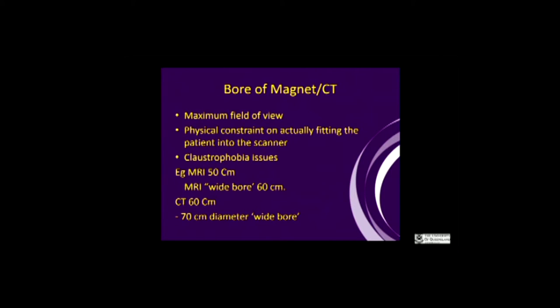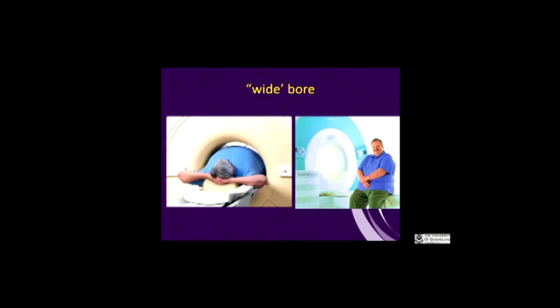The other physical effects are the actual diameter of the magnet or CT bore. 50 centimetres or 60 centimetres is actually quite narrow for an obese patient. MR had a 50-centimetre bore and the wide bore is 60 centimetres, which a lot of people promote now — also for reasons of claustrophobia. MR and CT are not actually that physically limited by weight; you just can't fit the patient in the scanner. If you can get them into the scanner, you can get an image. If you can't, you can't get anything. CTs are now up to 70 centimetres, so it is changing, though most equipment is not quite there yet.